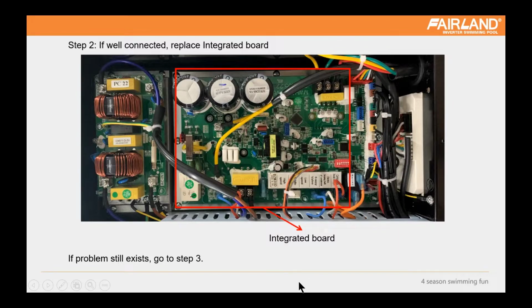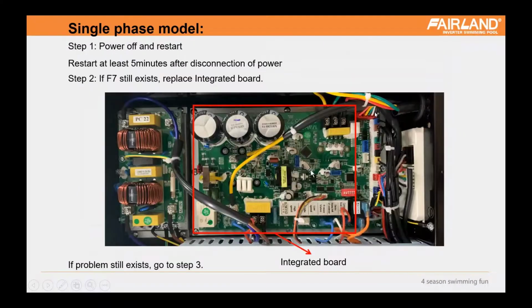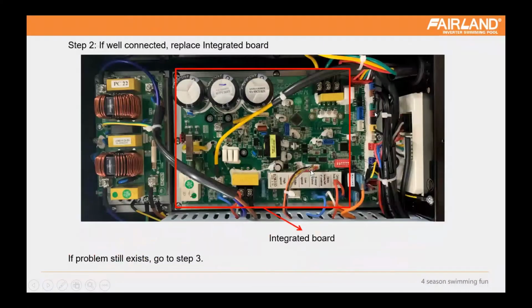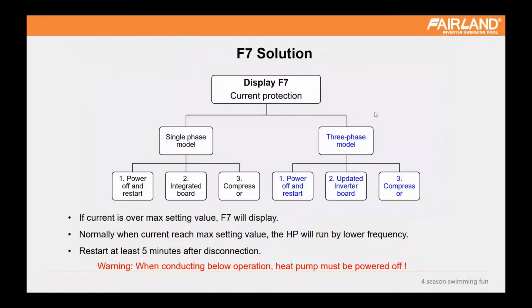Sometimes the customer will ask us if they can use the multimeter or other tools to do some detection on one of the terminals to check if it has a problem or not. Sorry to inform that the terminals we can detect are limited. Most of the time, we will simply replace the board, and no detection needs to be carried out. And F7 is current protection.